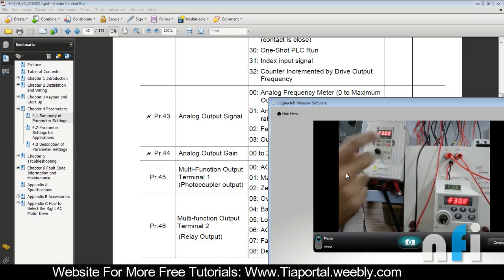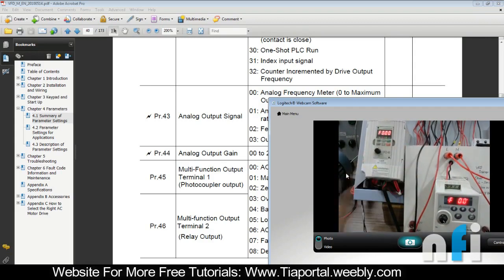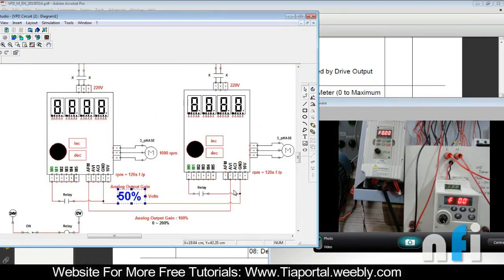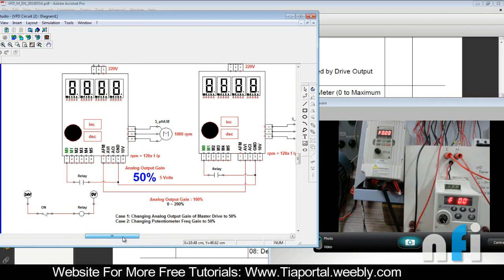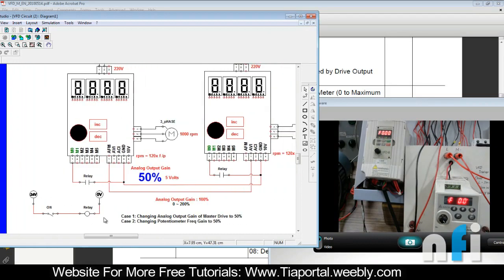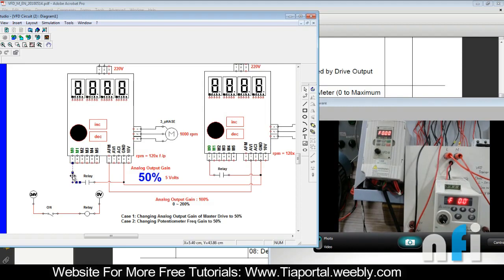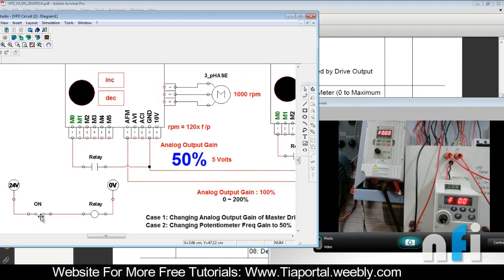Those are the gain settings — you can increase or decrease the gain. You can also connect as many drives in parallel using these AFM and AVI connections: connect the AFM of the master to the AVI of each slave drive. One more interesting thing — to synchronize start and stop as well, you can program your drive to accept an on signal from external control terminals with the source of operation set to external.